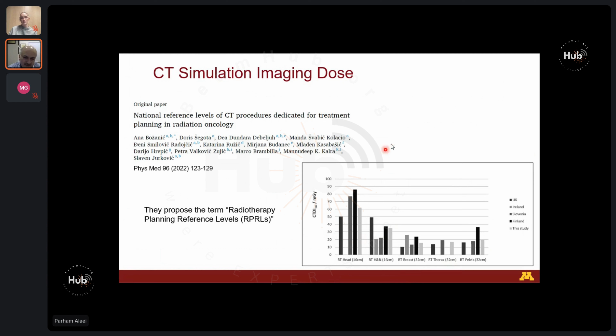So these are basically benchmarks that can be used. You can check your own CT scanner against what's out there, essentially measure CTDI volume if you have access to the phantom, of course, and compare to this. Again, it's not optimization, but it's some benchmarking of the CT doses. Now, as I mentioned before, I have borrowed some slides from a diagnostic colleague, Marco Brambilla. And so, again, it's interesting: can CT protocols used for treatment planning be adjusted to optimize image quality and patient dose?